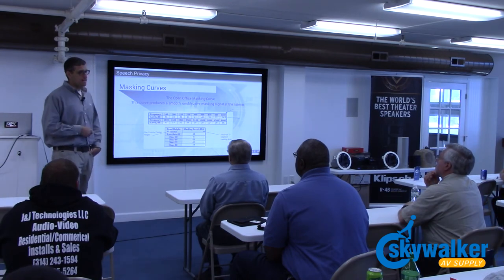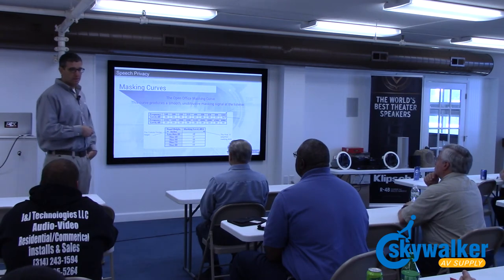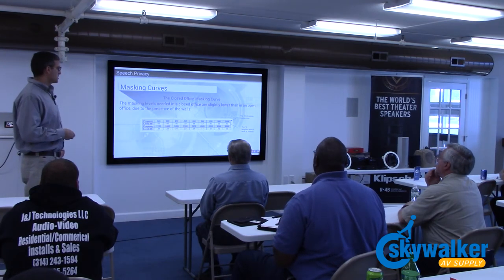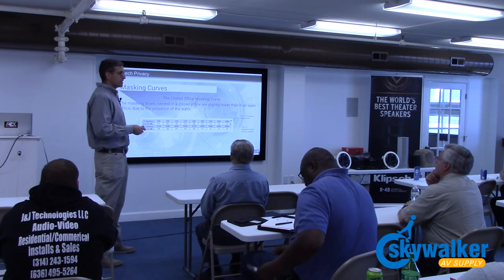As part of our sound masking design help, we will also give you this information so you can go out there and set it where it needs to be set in order to make it work. This is a closed office. Notice that we're 5 dB less at the 160 hertz range, and we're 8 dB less at 3.15. So in a closed office versus an open office application, your volumes and levels are going to be different by frequency. That's why if you're going to get into sound masking as a regular thing, having the right equipment is super important, and making sure that you're selling the customer the right stuff is very important.